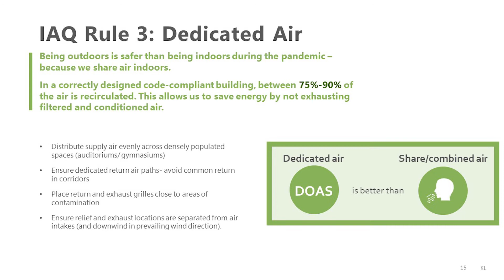So all those things need to be considered. We're getting a lot of requests this year from owners, especially schools: can we bring in more outside air, or do once-a-week cleaning of the entire classroom to replace the air when kids are gone for a couple hours? But then we have to think, do we have enough capacity in the coil to heat, cool, and dehumidify that air? If not, we may need to replace the entire coil or air handling unit, and that's not always possible.